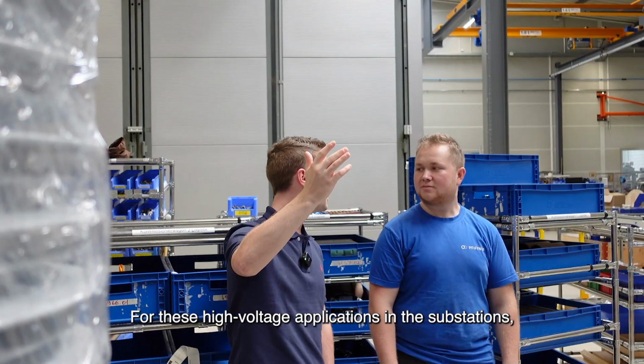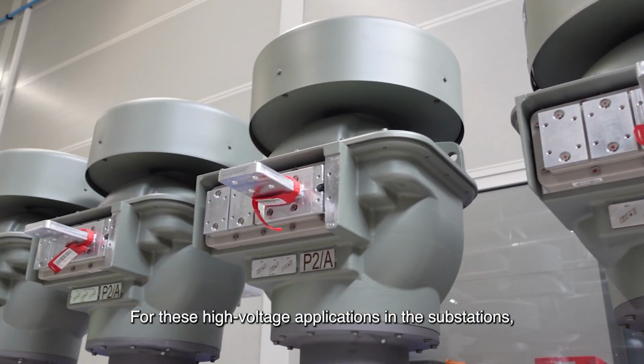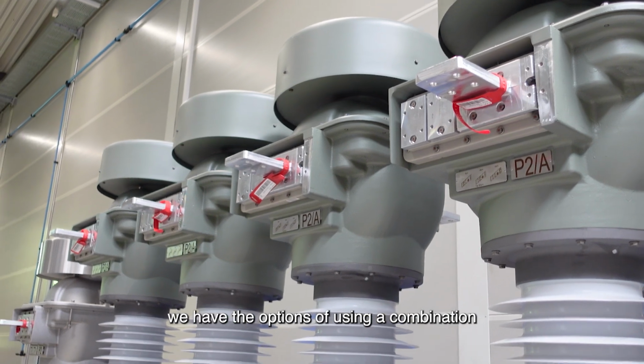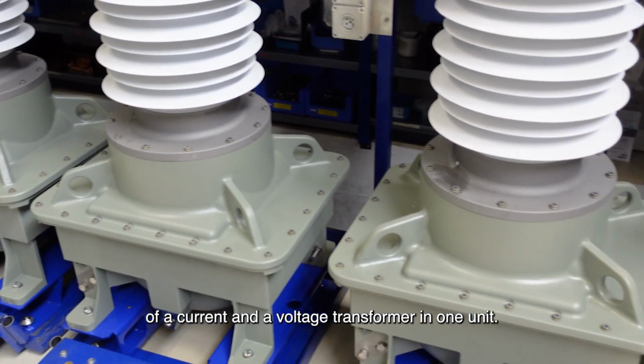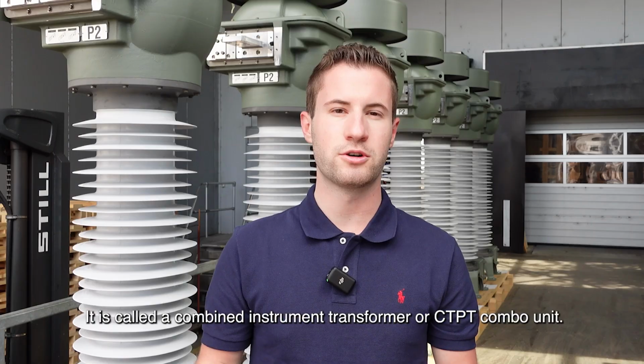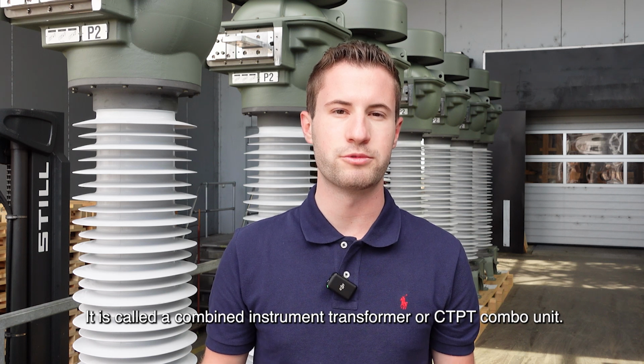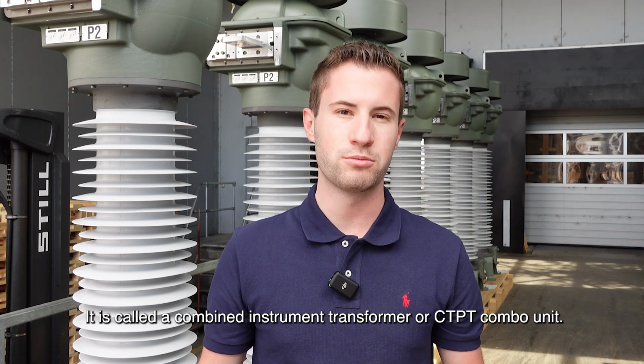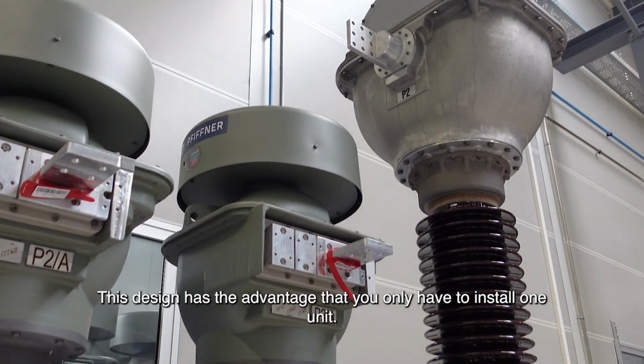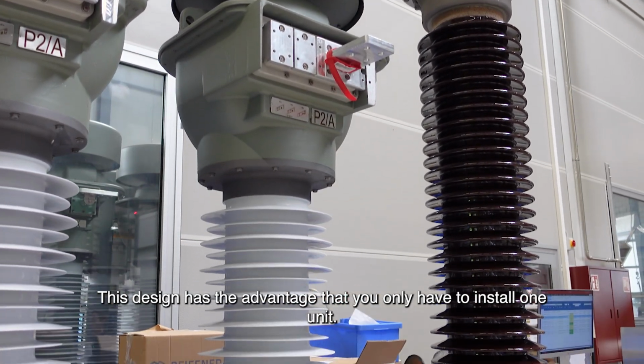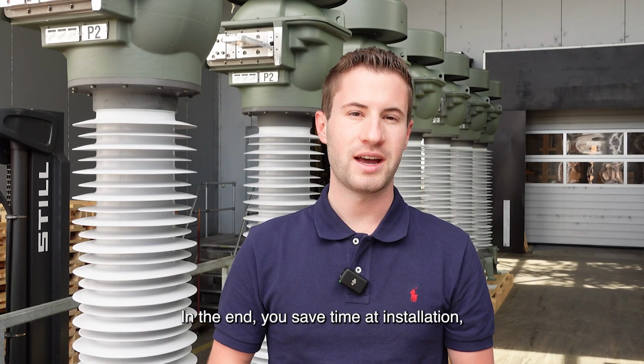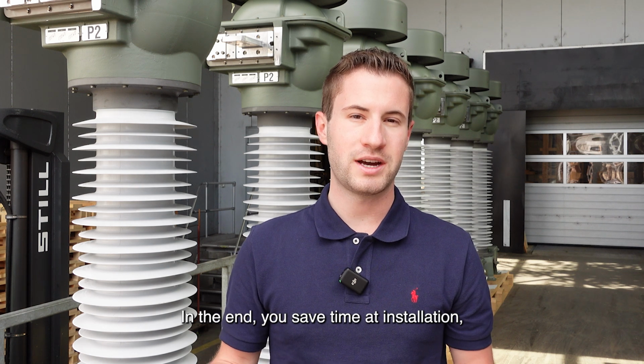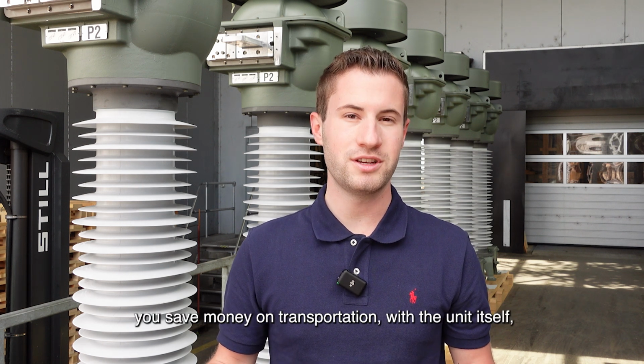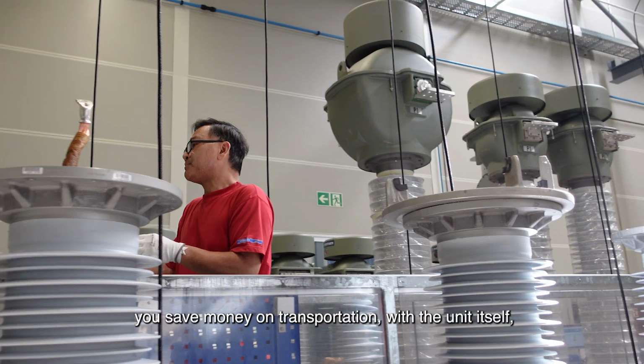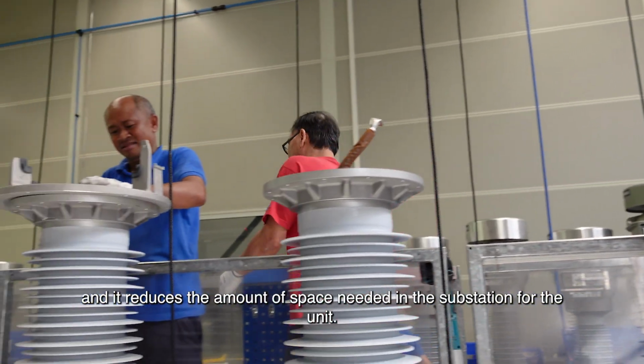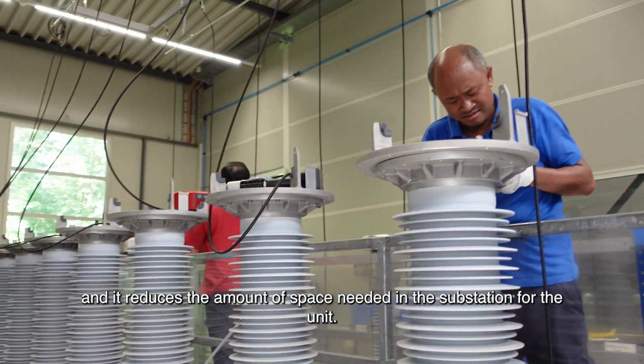For these high voltage applications in substations, we have the option of using a combination of a current and a voltage transformer in one unit, called a combined instrument transformer, or CT-PT combo unit. This design has the advantage that you only have to install one unit. You save time at installation, you save money on transportation, and it reduces the amount of space needed in the substation.